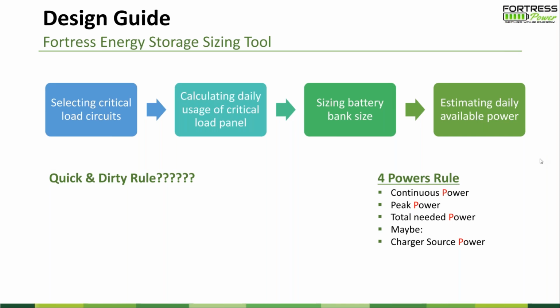The quick dirty rule is: if you have an inverter decided, for example a 5 kW continuous power inverter, you take that rated power times 2 and add 'H' at the end, becomes 10 kilowatt hours. That's the battery bank size you usually need. I can tell you there's a 70% chance you'll hit the target, so you won't size up a system too wrong.